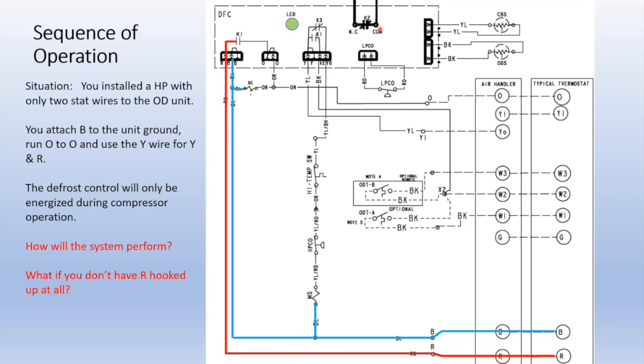Another thing is maybe you don't have R on there at all. It's still going to work without R hooked up. The outdoor unit is still going to run, but it's never going to go into a defrost, because R is what's powering all the logic in here. So if you don't have a green light, you don't have R hooked up, or there's an issue with the R wire.